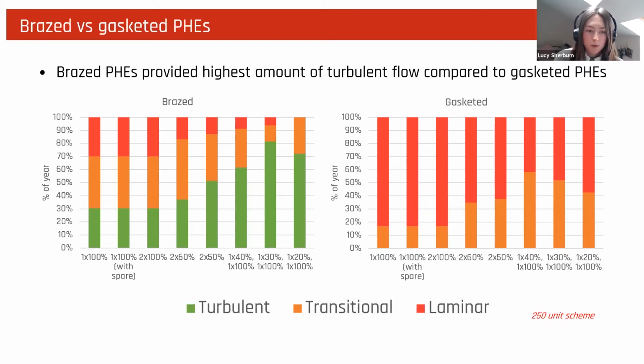So we want as much turbulent flow as possible. Using the hourly load model, at each load point within that, I was able to tell whether the plate heat exchanger selected was operating at turbulent, laminar, or transitional flow. Transitional flow is just the bit between the two. The graphs compared different size plates for both brazed and gasketed solutions, and you can see the breakdown of those different flow regimes across the year. I think it's pretty clear to see that brazed plate heat exchangers provided the highest amount of turbulent flow in comparison to gasketed plate heat exchangers. Next slide, please, Gareth.